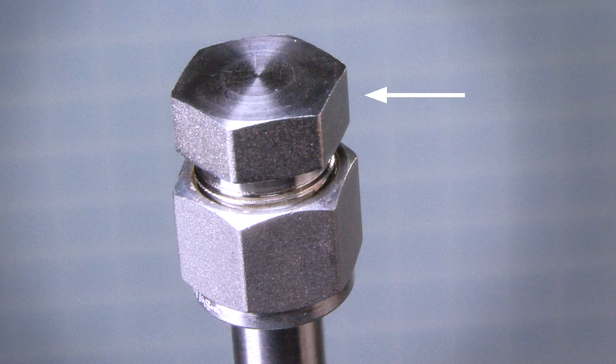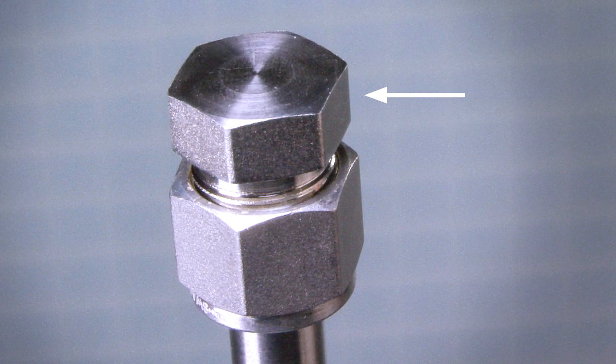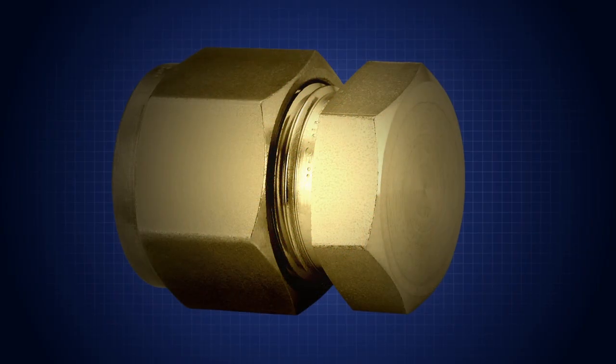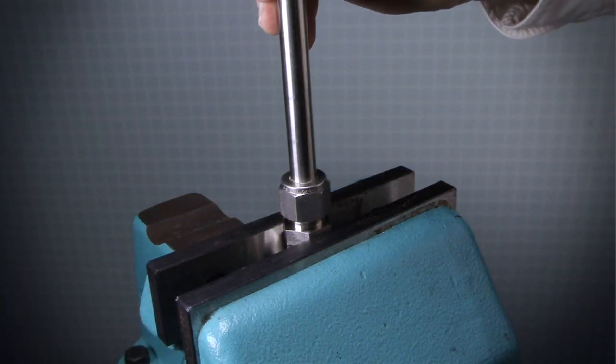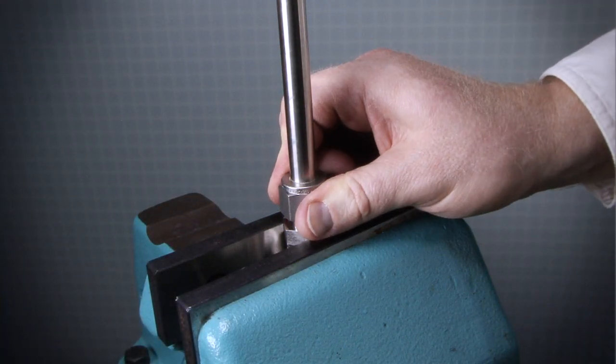Swagelok caps can be used to block off the end of a tube run when desired. Caps are installed using the installation instructions for a Swagelok tube fitting. Fully insert the tube into the fitting and against the shoulder. Rotate the nut finger tight.